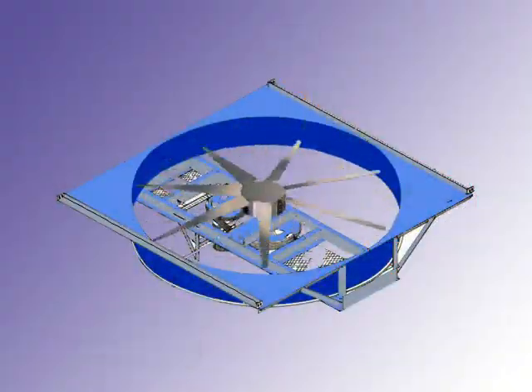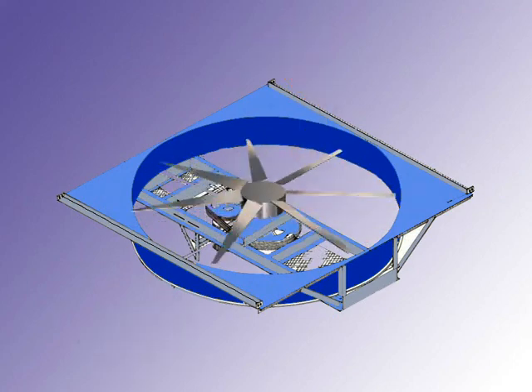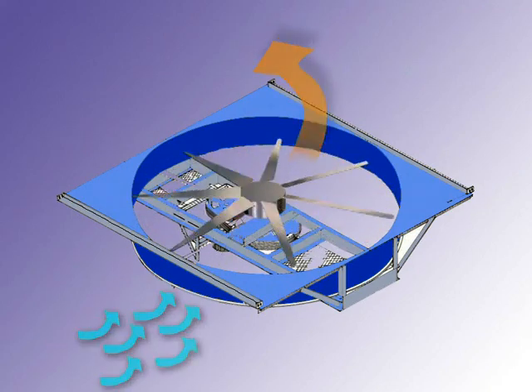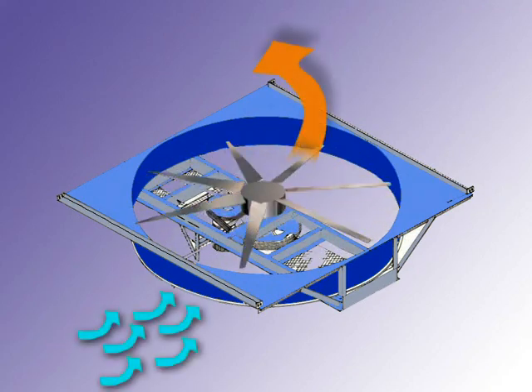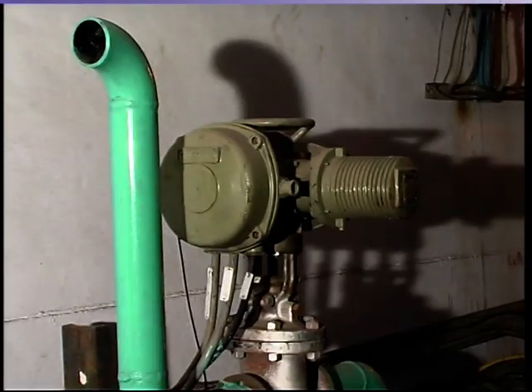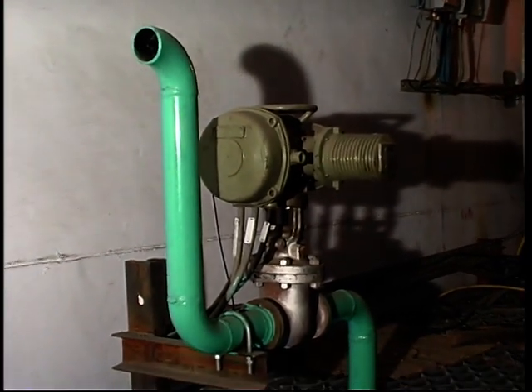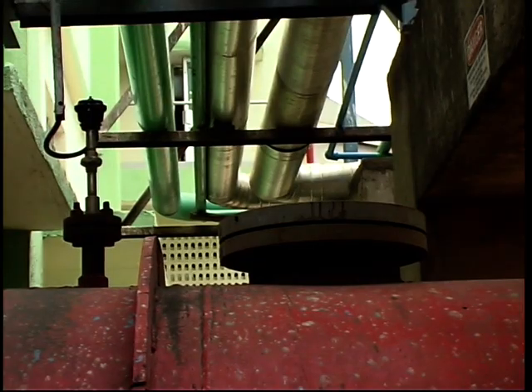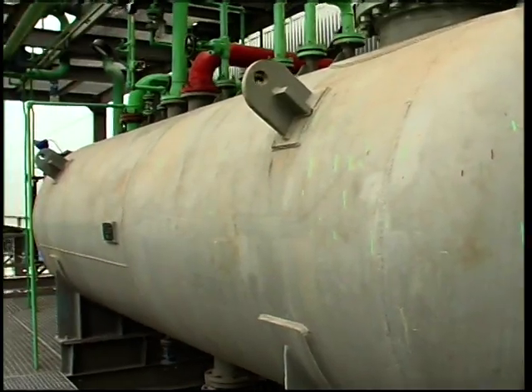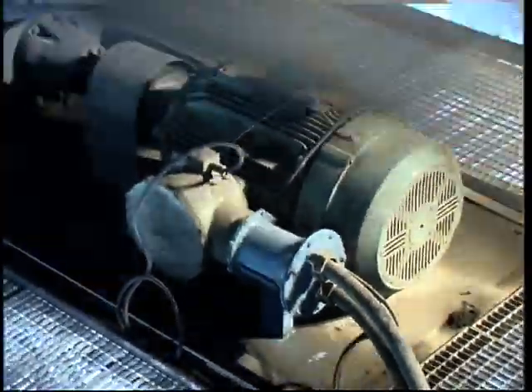By definition, an air-cooled steam condenser requires air. More precisely, it requires large quantities of air distributed uniformly and efficiently. To achieve these goals, Paharpur furnishes mechanical equipment designed specifically for air-cooled condenser application. DRH condensers achieve low power and noise by using large diameter multi-bladed Paharpur fans. The fans are driven by high-quality TEFC induction motors through Paharpur's spiral bevel-cum-helical gearboxes.